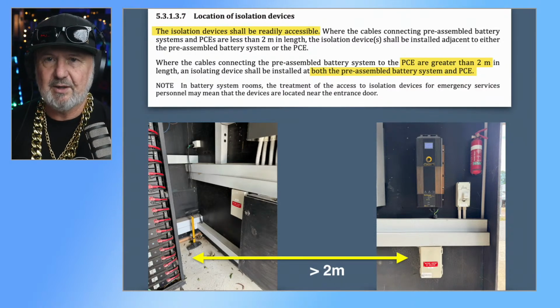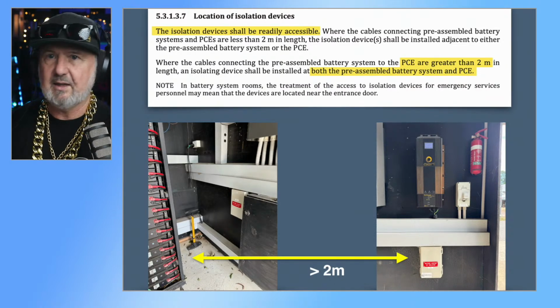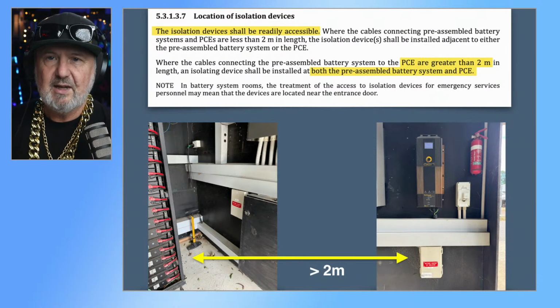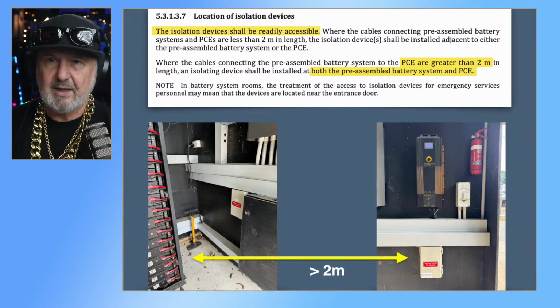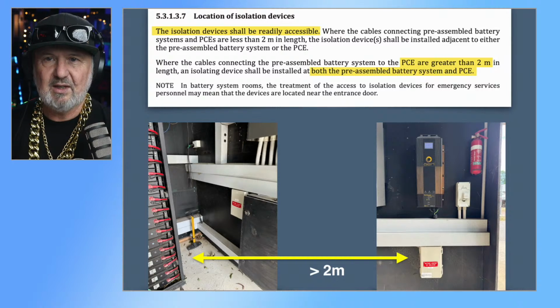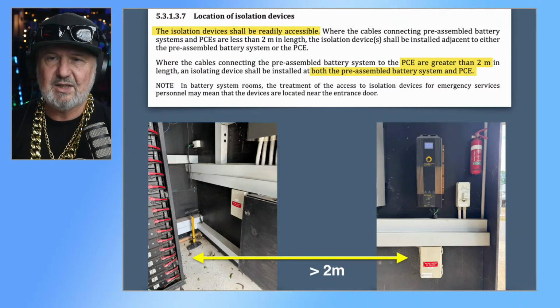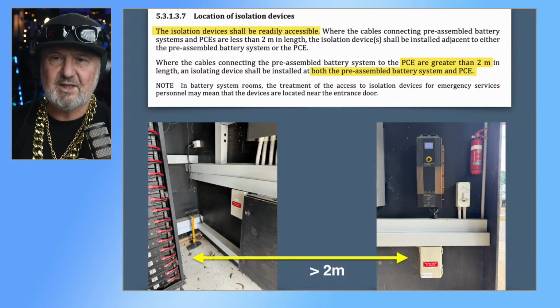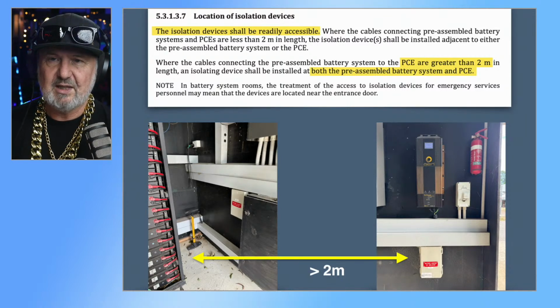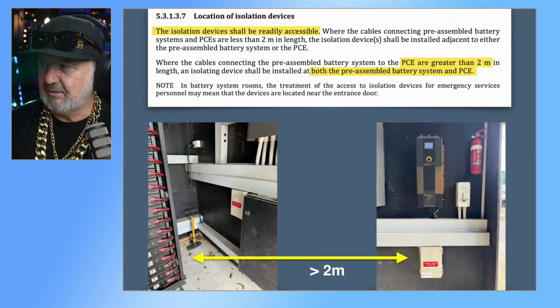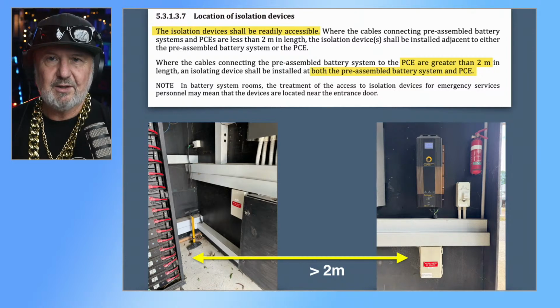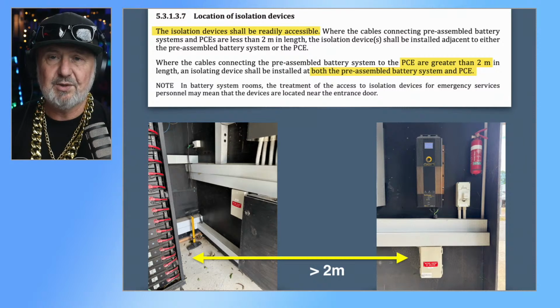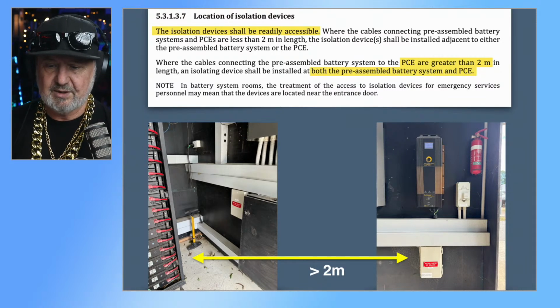So in the pictures down below here, and I can't use my mouse because it's on the screen, if you look at the picture on the left, there's our battery system, but the MPPT is 6 meters away, and so it needs to have its own isolator adjacent to it. So it's got a DC isolator right next to the PCE, and of course the battery system has its own means of isolation. So there you go, 2 meter rule. So try and keep your battery close to your PCE, and you only need one isolation point. But if it's more than 2 meters, you're going to need 2 isolation points.